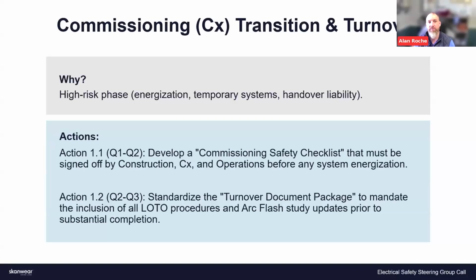These details come out when we're having meetings, and sometimes they're included in the commissioning plan—like having bi-weekly meetings to cover issues, or a process where 4 days prior to energization all the paperwork gets reviewed, that's your deadline. Then within 24 hours of energization you do your final pre-energization inspection. Maybe 36 hours is more appropriate for your site, but come up with hard and fast rules from the get-go and say, this is our process, this is how we'll do it every time.